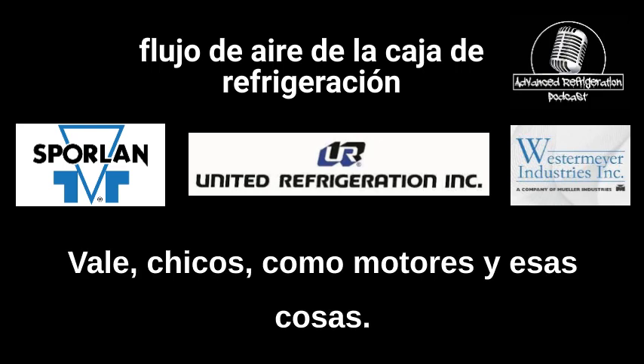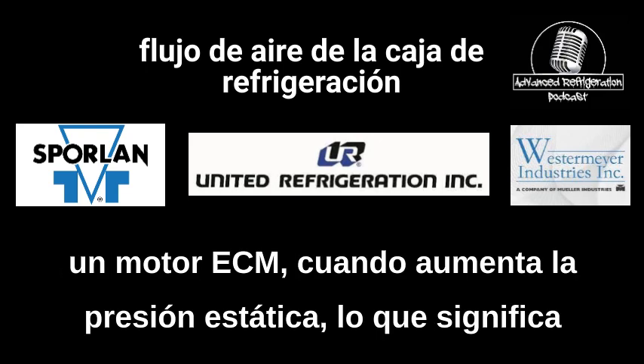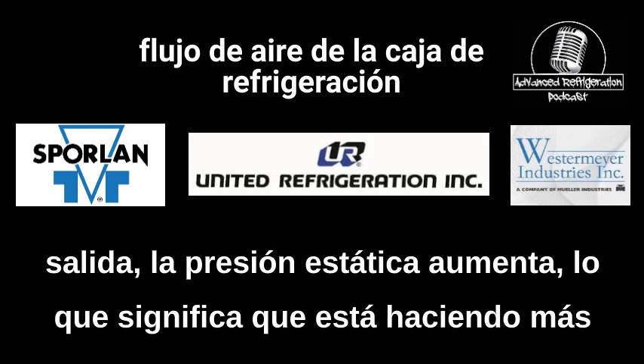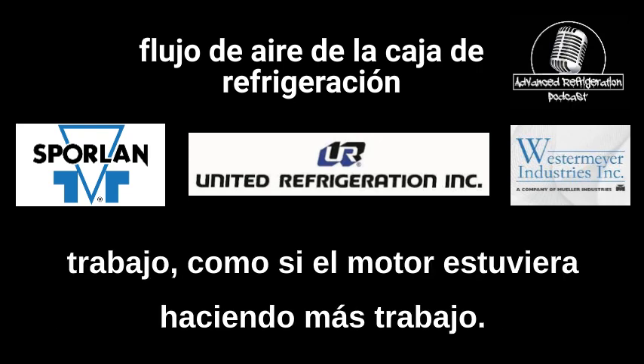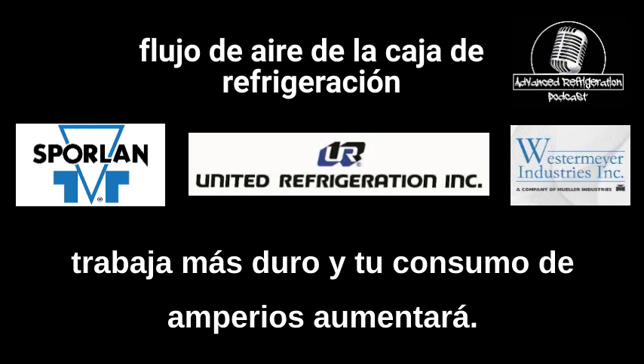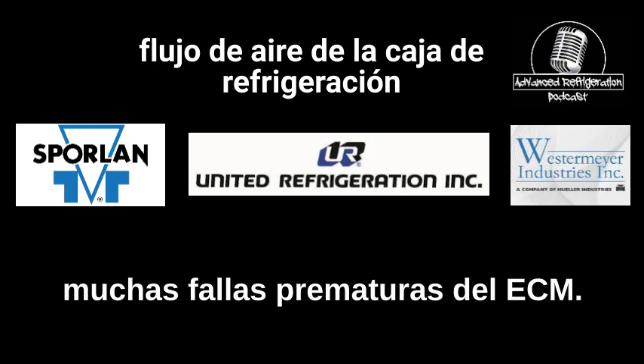Okay, guys, now motors and stuff. When you're looking at ECM motors, when the static pressure increases, meaning there's a blockage on the inlet or the outlet, the motor is doing more work. An ECM motor will speed up and try to work harder, and your amp draw will increase. And that's why you'll see a lot of premature ECM failures.